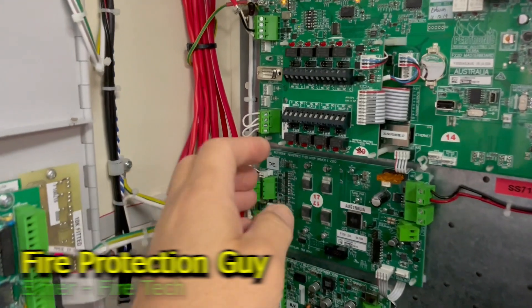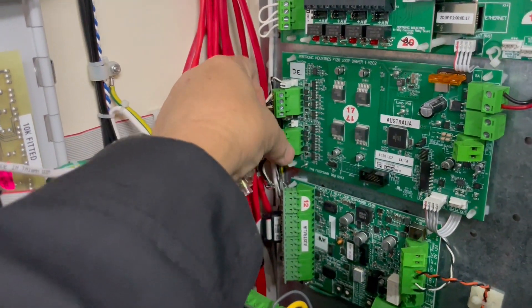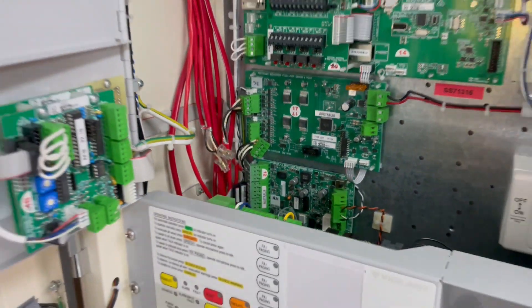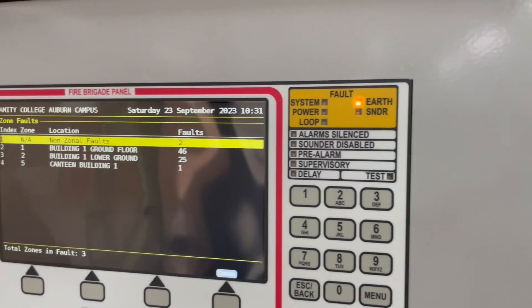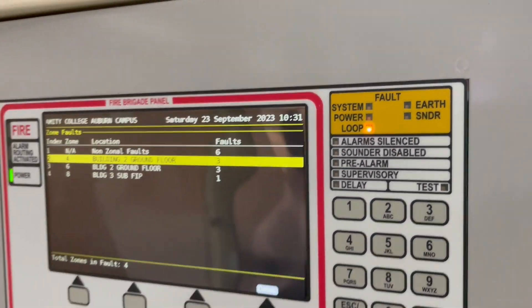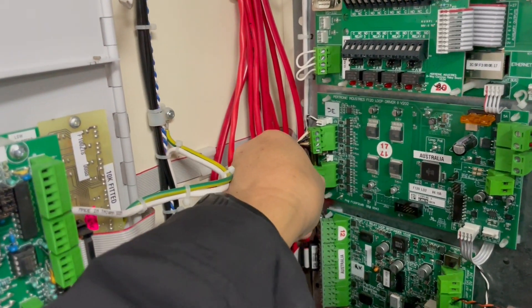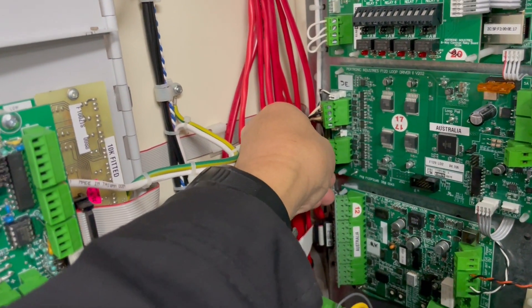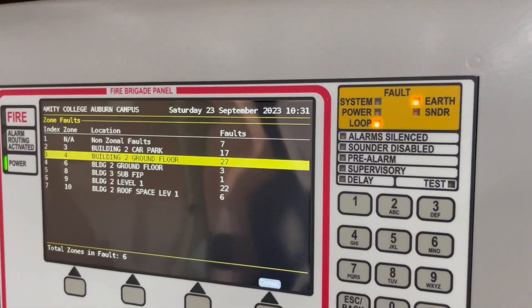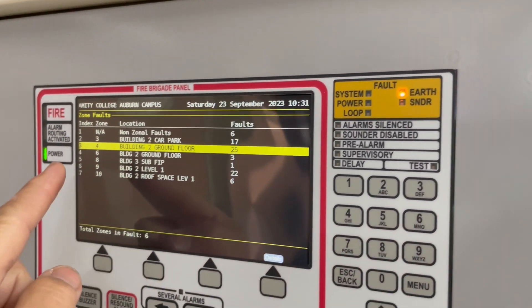Let's plug that thing back. Let's plug out loop number two. Let's see what's happening. Earth fault is gone. So that's where the earth fault is coming from. Let's plug back loop number two and check if the earth fault returns. Yes, it does. So we are now concentrating on loop number two.